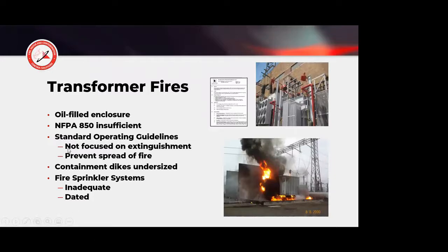So this is what I just mentioned. NFPA 850, it's insufficient for fire suppression. The containment dikes here around the transformer are undersized. In the standard, it says to contain the hydraulic oil plus 10%. And now we're going to spray plain water over the top of this transformer, overflow the containment. In fact, Dominion had one where the sprinkler system overflowed the containment, but the fire department wouldn't let them shut down the sprinkler system. So they had flammable hydraulic oil going across their parking lot towards their turbine deck. They were like, ooh, this is not the way to go.